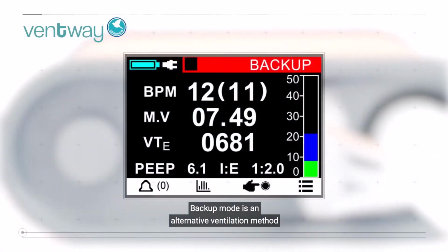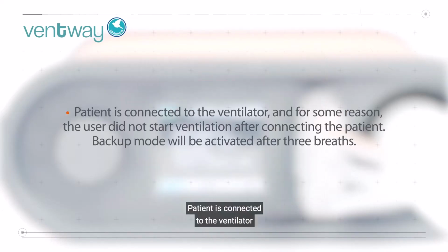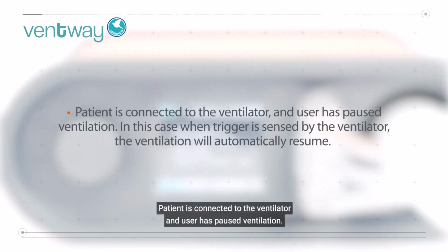Backup mode is an alternative ventilation method taking place in the following situations when the ventilator patient circuit is connected to the patient. Patient is connected to the ventilator, and for some reason, the user did not start ventilation after connecting the patient. Backup mode will be activated after 3 breaths. Patient is connected to the ventilator and user has paused ventilation. In this case, when a trigger is sensed by the ventilator, ventilation will automatically resume.